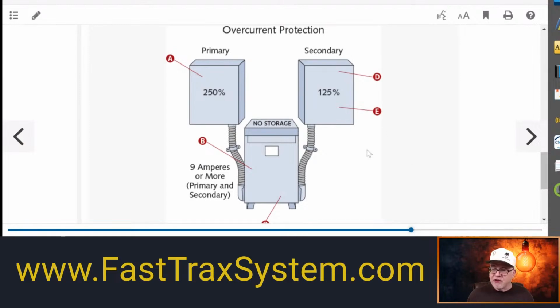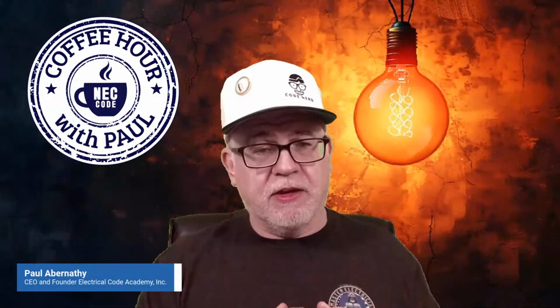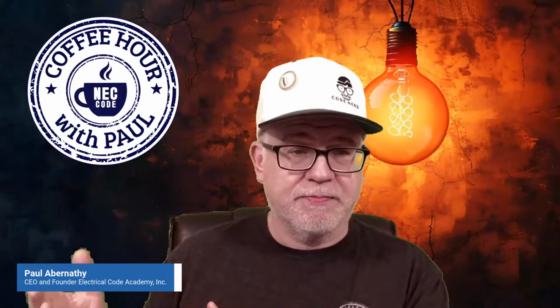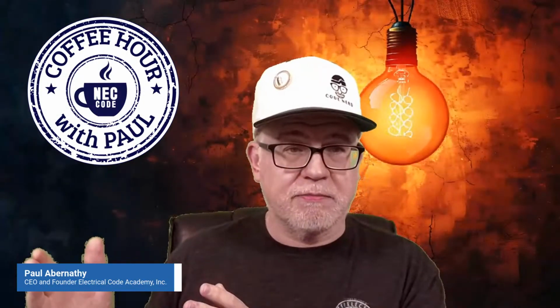Just remember that these conductors have to be sized. Even though we know that this is a limiting factor, it has to be sized based on what? The rating of the device that it terminates into. That was under the 10-foot rules for secondary conductors. Now, again, we weren't going to go into secondaries, but the reason I bring this up is this is maximum. In the field, no logically minded engineer is going to do this at the maximum. They're not going to do it at 300.